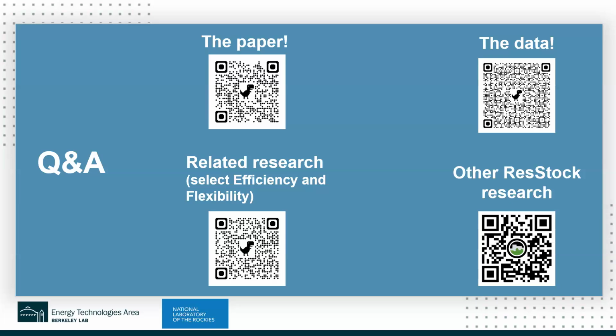Did we assess how often panels are sized to match the utility service connection, and what happens if you upgrade a panel—do you also have to upgrade the service connection? We didn't have data on typical utility service connections to homes; that's a hard piece of information to find. Anecdotally, service connections may be larger than existing panels, so you might go from a 100 amp to 200 amp panel but already have sufficient electrical service. If you do need higher service, it can require additional costs, so this is an opportunity for additional research to understand the disposition of electrical service on the utility side.